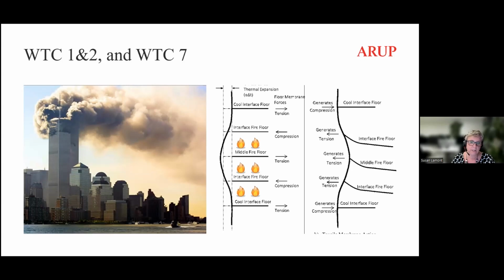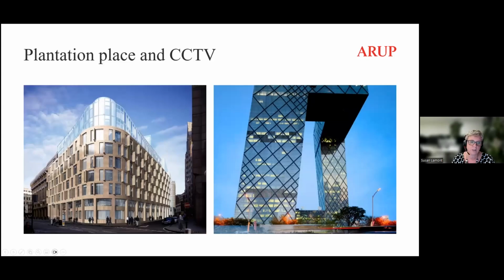By 2001, we were able to design structures in response to fire in the same way structural engineers design for live loads such as wind and seismic. Importantly, we could quantify robustness and design knowingly, rather than relying on standard fire resistance tests of a single beam or column.